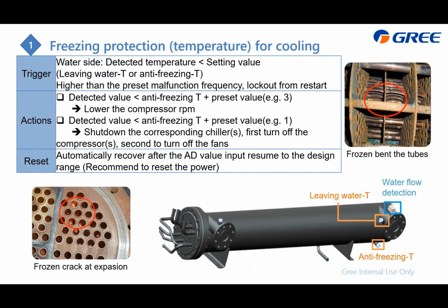Next is the freezing protection, which is the temperature for the cooling. As you know, for the cooling, if we make it too cold, it makes heat exchange with the water. For the water, the most problem is it will be frozen, which becomes ice. And from this picture, you can also find that if it becomes ice, it will damage the inside components, which is the shell and tube heat exchanger. You can see from this picture, the freezing makes it bent, and also from this, we make it crack.